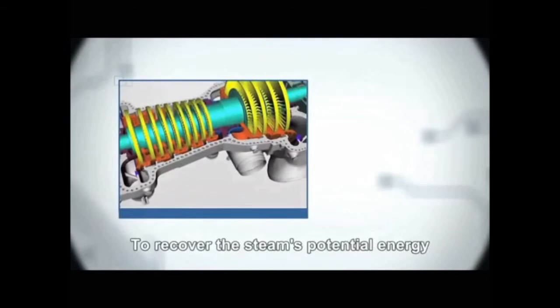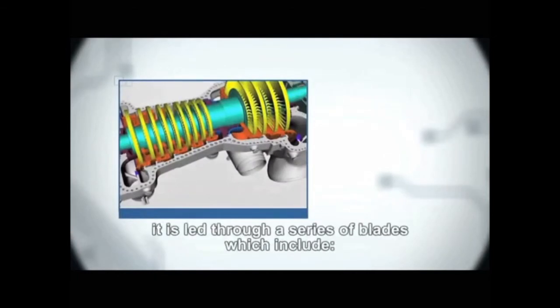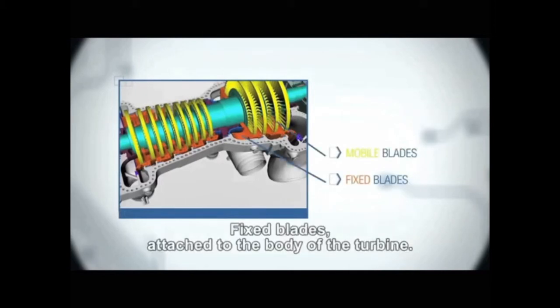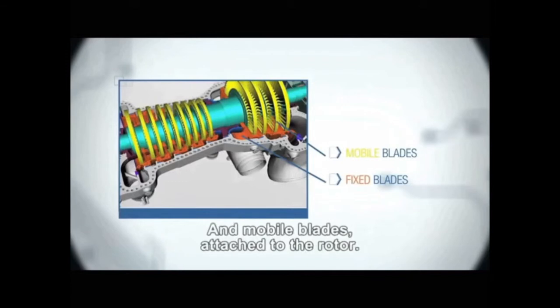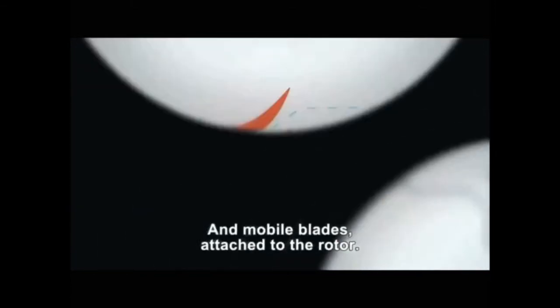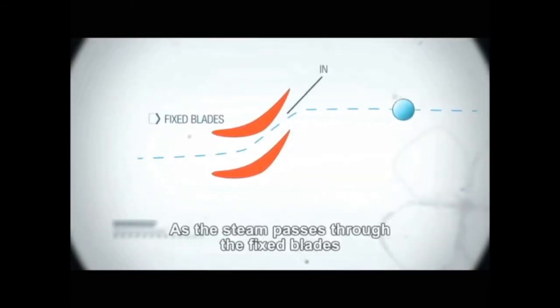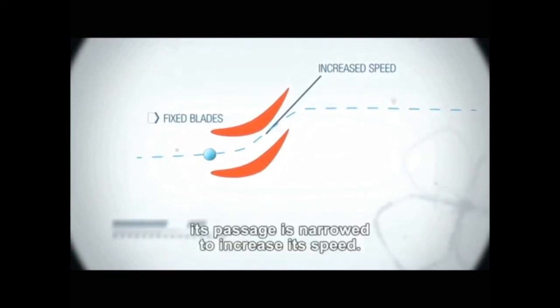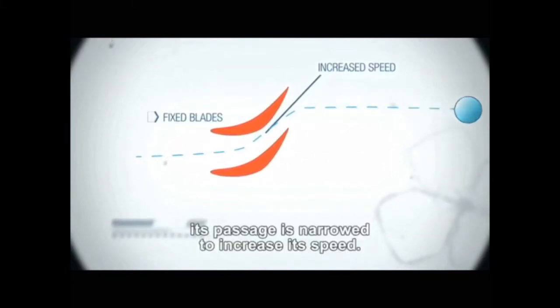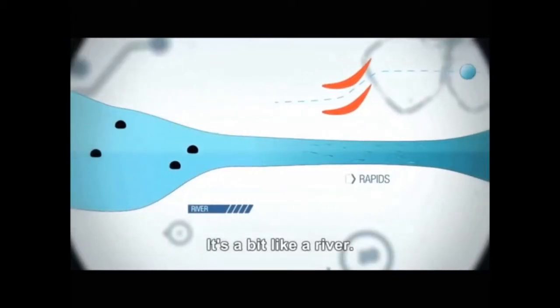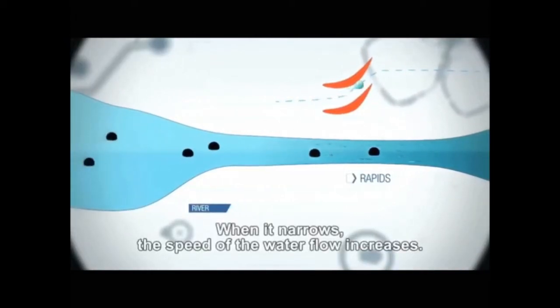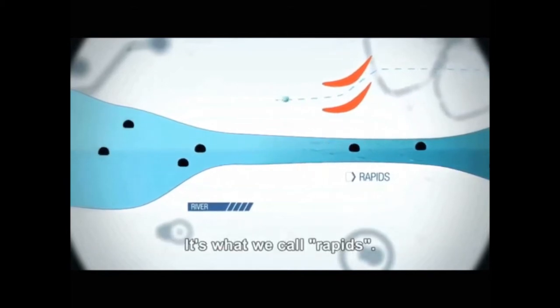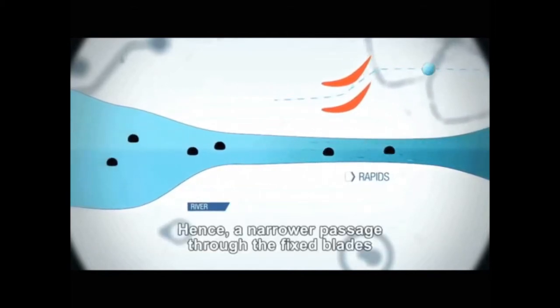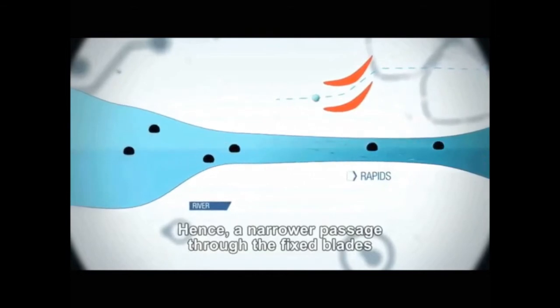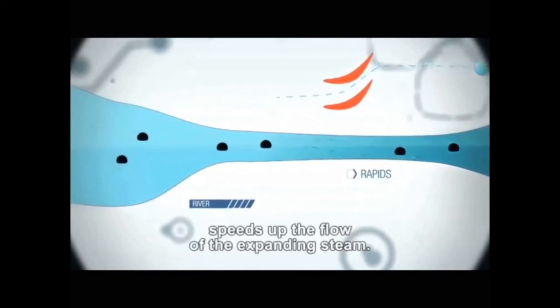To recover the steam's potential energy, it is led through a series of blades which include fixed blades attached to the body of the turbine and mobile blades attached to the rotor. As the steam passes through the fixed blade, its passage is narrow to increase its speed. Like a river, when it's narrow, the speed of the water flow increases. It's what we call rapids. Hence, a narrower passage through the fixed blade speeds up the flow of the expanding steam.